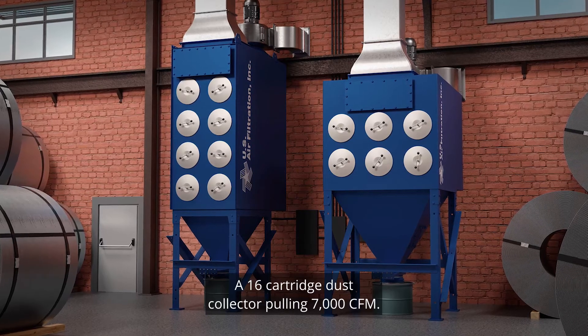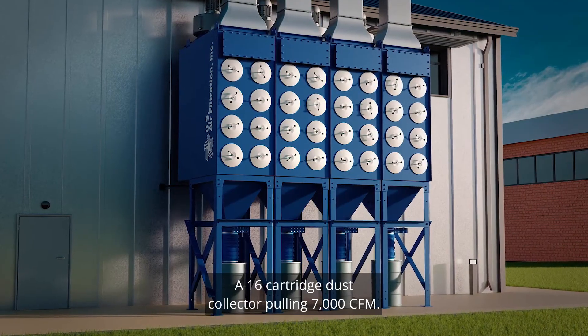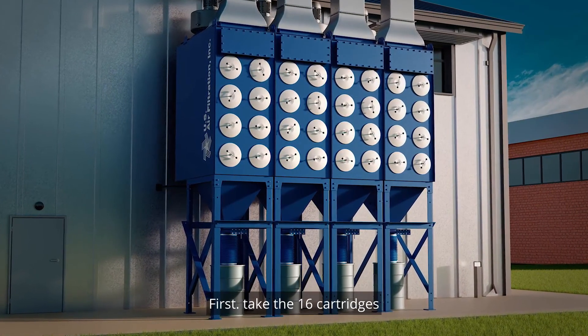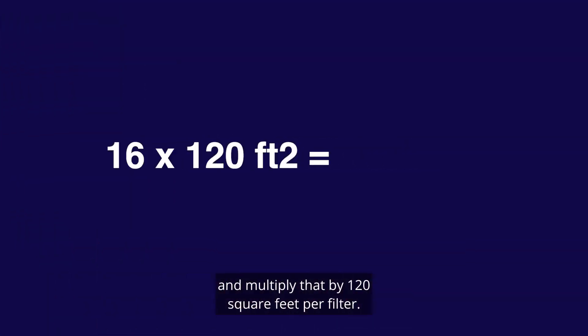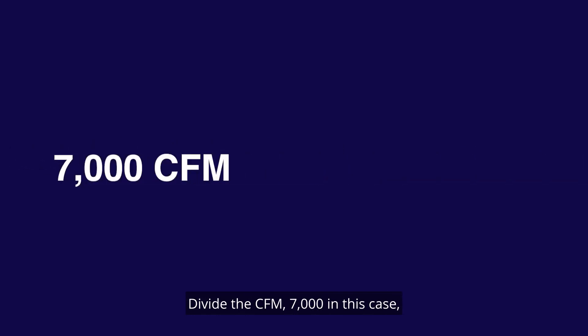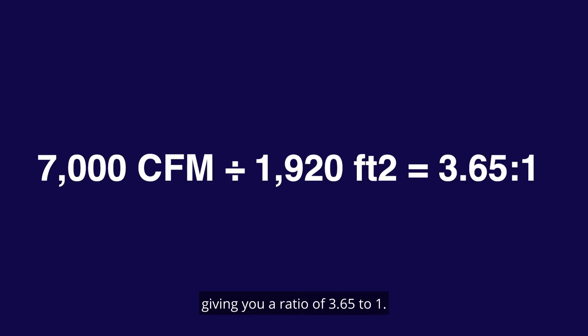Here's an example: a 16-cartridge dust collector pulling 7,000 CFM. First, take the 16 cartridges and multiply that by 120 square feet per filter, giving you 1,920 square feet. Then divide the CFM — 7,000 in this case — by the 1,920 square feet, giving you a ratio of 3.65 to 1.